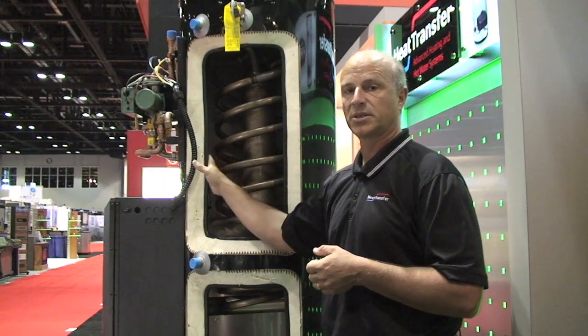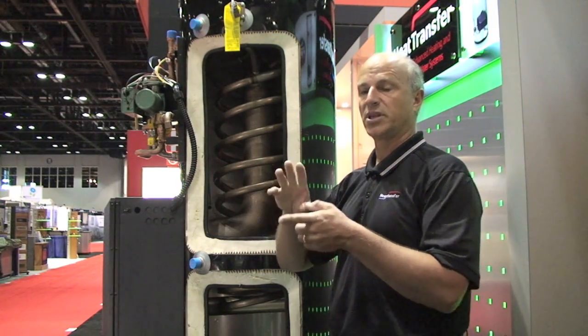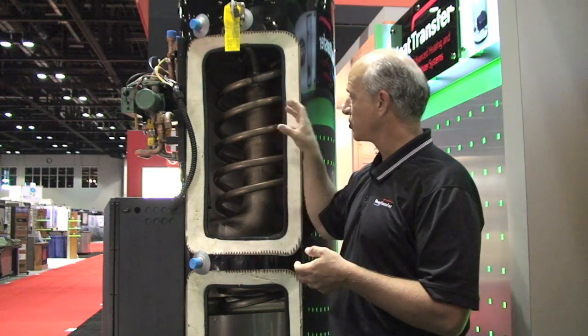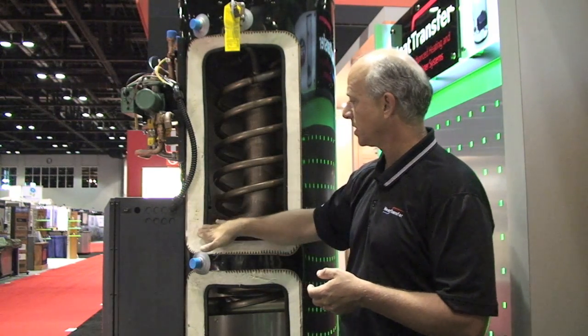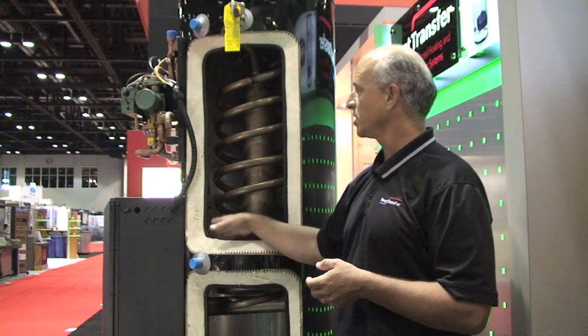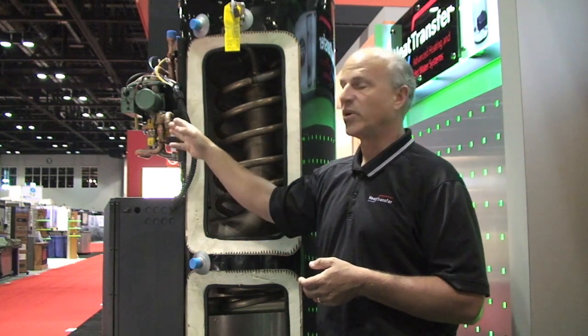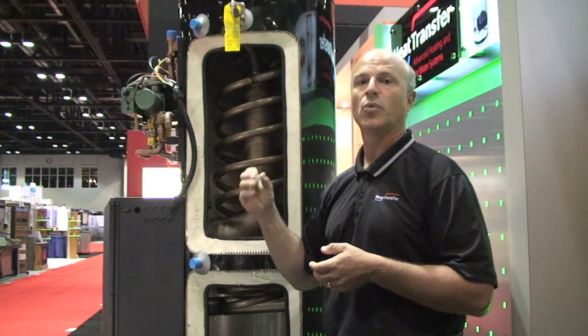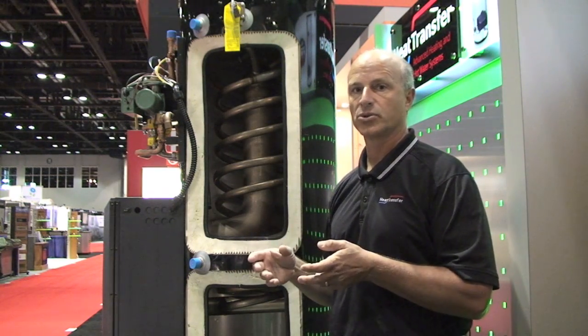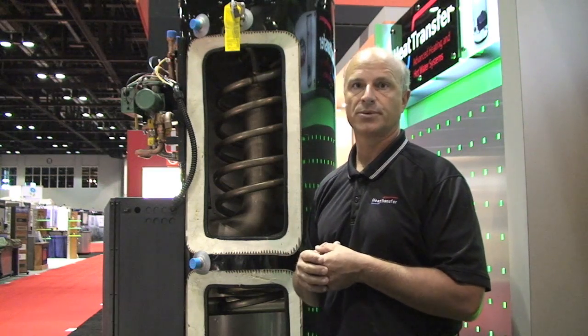This product's hydraulic stabilization not only helps on the domestic hot water production but also on the heat, because we have stored energy. We store it very efficiently with this high efficiency insulation and essentially we backfeed the system, modulating the pump only to give you the heat you actually need, eliminating a lot of the short cycling that occurs with conventional low mass boilers.